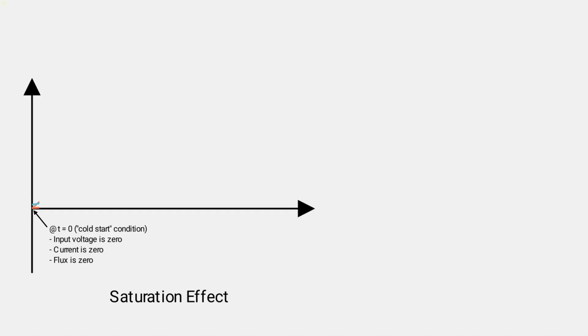And when that happens, the core can go into saturation. When the core saturates, the transformer loses its inductive reactance to current, so the only thing limiting the current is the small resistance of the copper windings. That's what causes the large inrush current, even with no load connected.